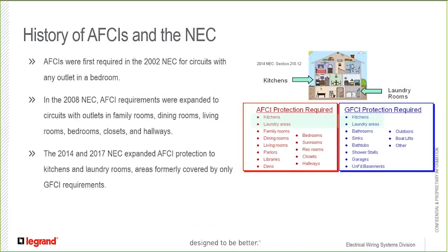Now, AFCIs, which stands for Arc Fault Circuit Interrupter, is a different type of device that is used to prevent fires in households due to faulty wiring of appliances, vacuum cleaner cords, or electrical wiring within the walls. It's a relatively newer technology as compared to GFCIs. They were first required in the 2002 National Electric Code for circuits with any outlet in a bedroom. In 2008, AFCI requirements were expanded to circuits with outlets in family rooms, dining rooms, living rooms, bedrooms, closets, and hallways, among other locations. And 2014 was the first year that AFCI protection overlapped into kitchens and laundry rooms, areas formerly covered by only GFCI requirements.